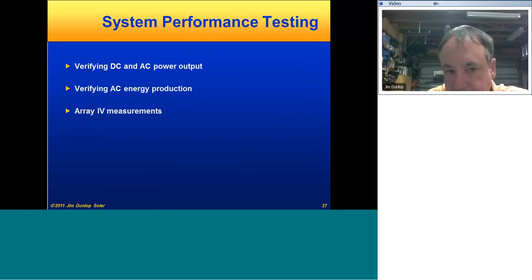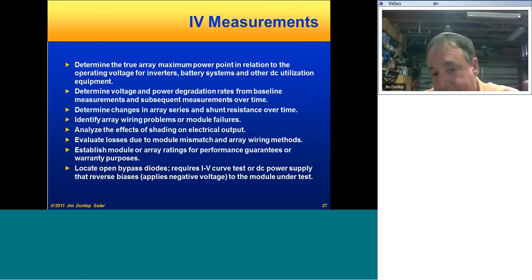On the performance testing, verifying the power output, energy production, IV measurements, these are certainly, the IV measurements, more advanced kinds of things that might be done to look at some problems within modules or something in a system. But certainly we're all doing the AC power and AC energy verification on the inverter, so no need to talk a lot about that. Some of the things IV measurements can do for you, and I guess Seaward's coming out with a unit, Solmetric makes one, help you determine whether you're tracking max power properly. It's not certain that all inverters are doing that great a job with that. They may operate at 97% efficiency, but if they don't track maximum power, that's a 90%. The efficiency doesn't mean much.